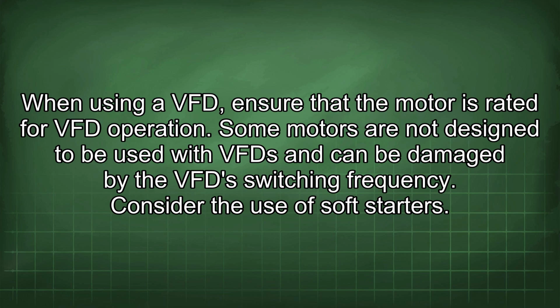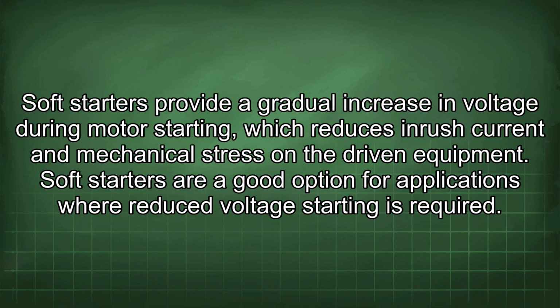Consider the use of soft starters. Soft starters provide a gradual increase in voltage during motor starting, which reduces inrush current and mechanical stress on the driven equipment. Soft starters are a good option for applications where reduced voltage starting is required.